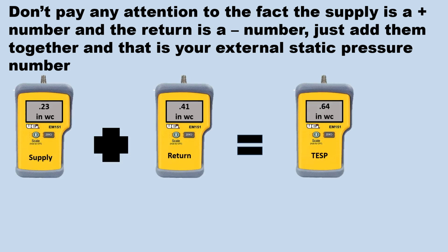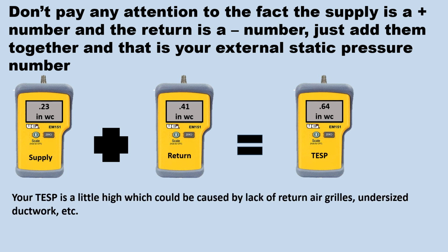So we see here that we have a supply of 0.23, a return of 0.41, and a 0.64 total external static pressure. Your total external static pressure is a little high, which could be caused by a lack of return air grilles, undersized ductwork, that kind of thing. The advantage of testing with a single port manometer is you already have each individual reading and know which side is causing the problem. If we only had a reading from a dual port manometer, you would need to go back and test each one individually to see which one is the problem.